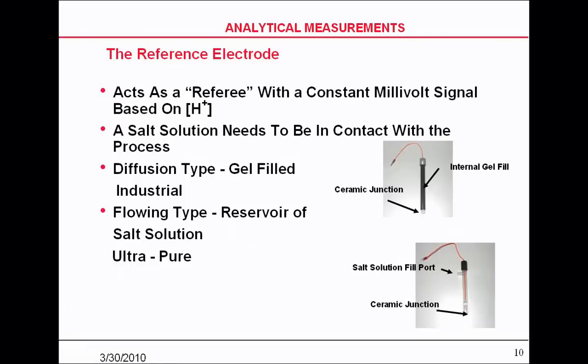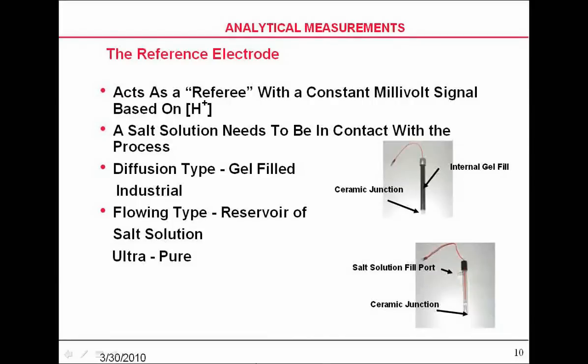There are basically two types of references. One is the top picture, and the other is the bottom. The one on the top is a small industrial reference electrode. In these cases, they have a finite amount of potassium chloride in them. They're filled when they're shipped from the plant with potassium chloride or a reference solution. The reference electrode acts as a referee, attempting to supply a constant millivolt signal back to your electronics.